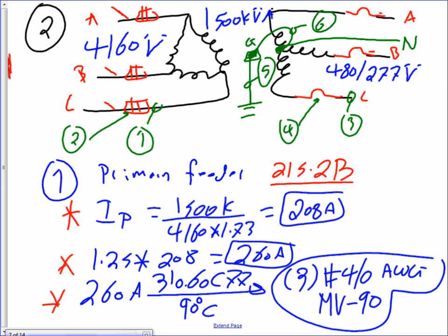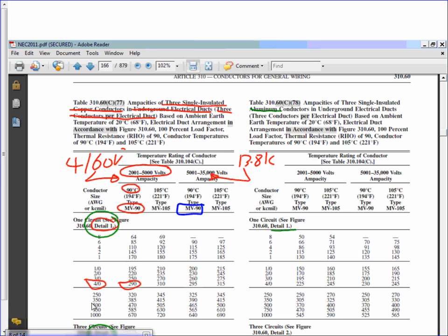Okay, here's the table that we went to. Okay, this is the table. Please highlight this table. That's the one I'm going to go to. It says 3 single insulated copper conductors in underground electrical duct, 3 conductors per electrical duct. So that's the assumption. The assumption is you're going to put them in a conduit underground, 3 conductors. That's not in the air, that's underground. That's a typical installation. Okay, I want to bring to your attention, guys, how to read this table.